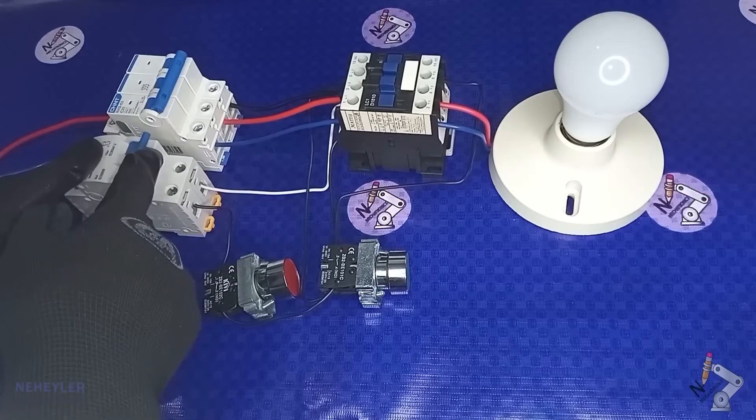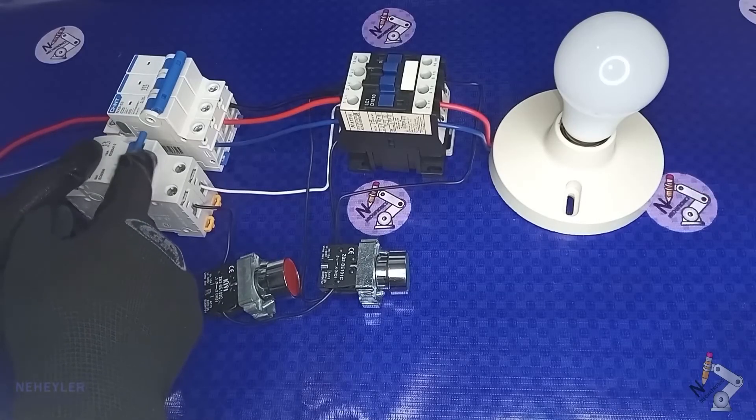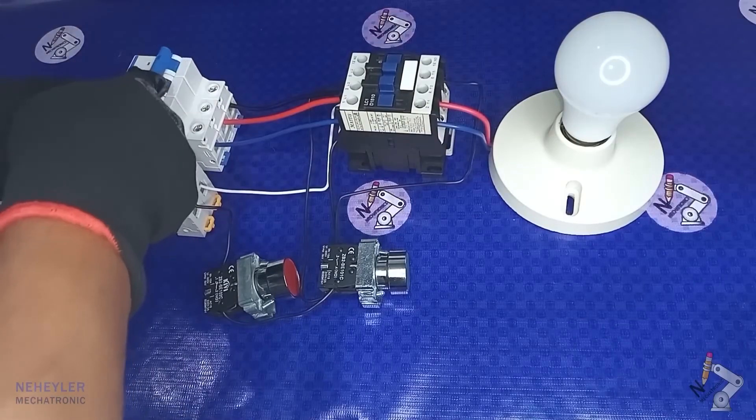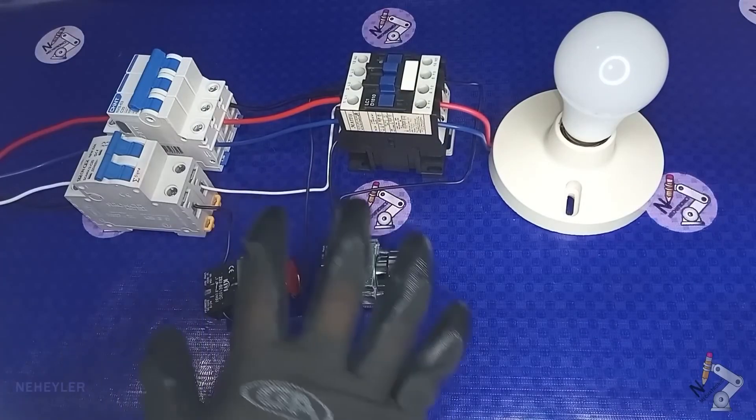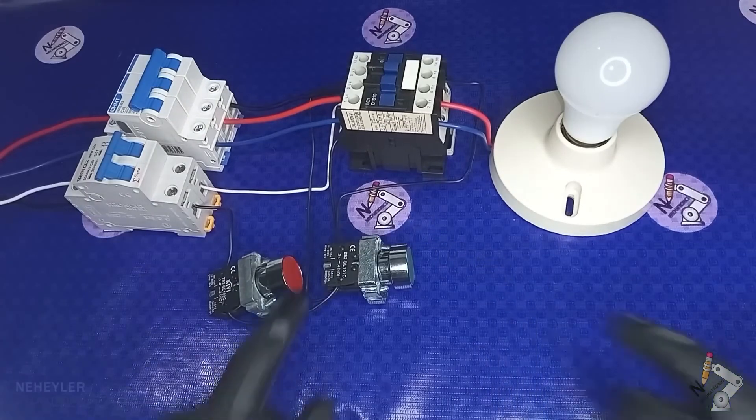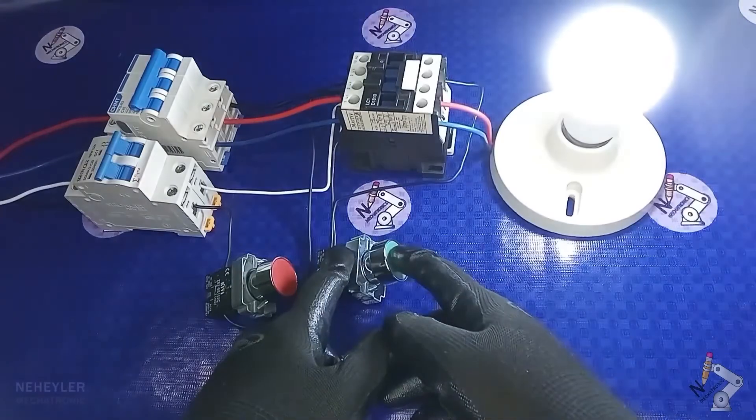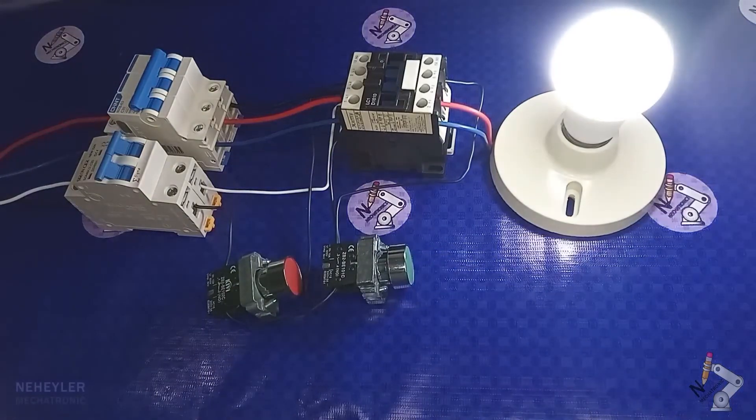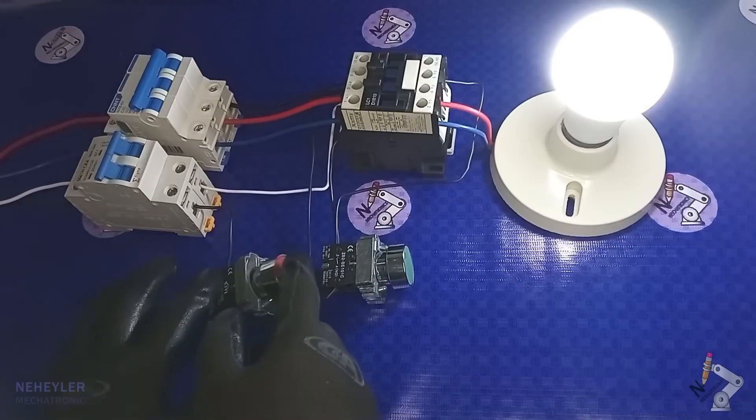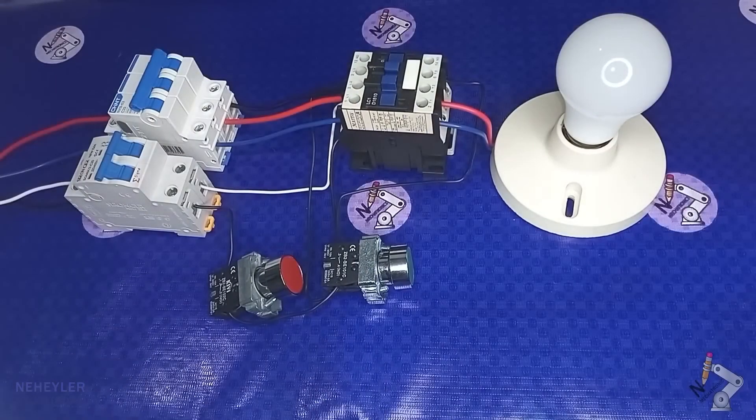We test the circuit, we turn up the switch's lever. Up to this point, we already have everything energized, ready to do the corresponding test. We press the start button, and as we see, the light bulb turns on. This means that the contactor coil remains stuck and will remain so until the stop button is pressed. We press the stop button, and as we see, the light bulb turns off, since the contacts of the contactor return to their default position, which is open.